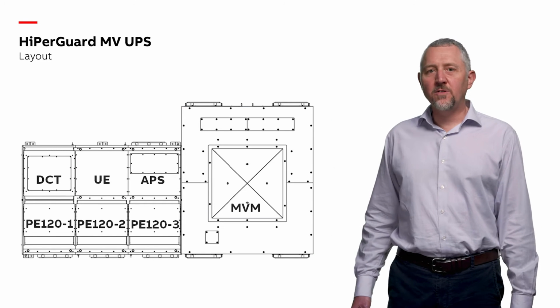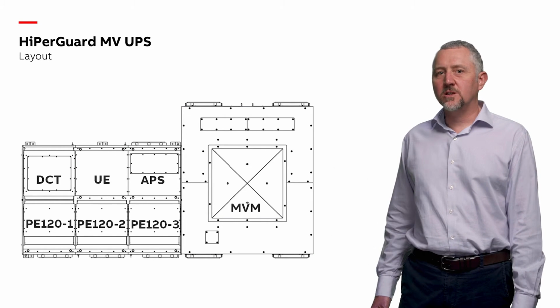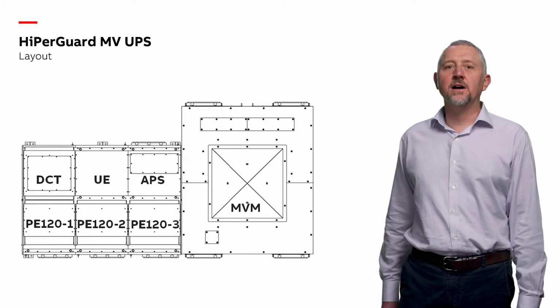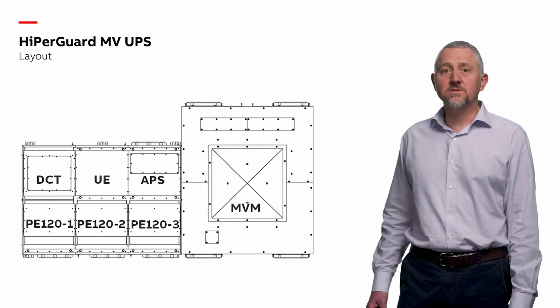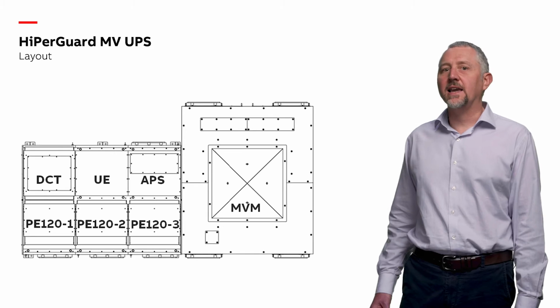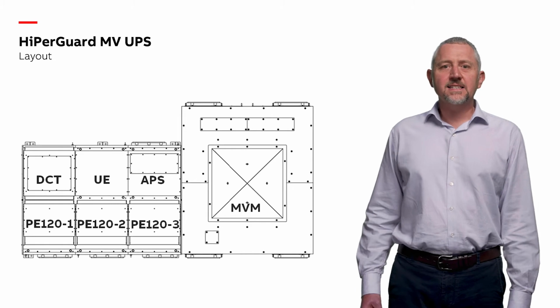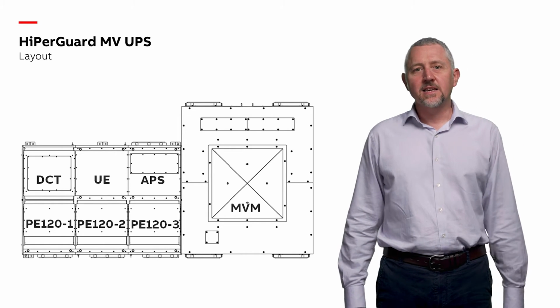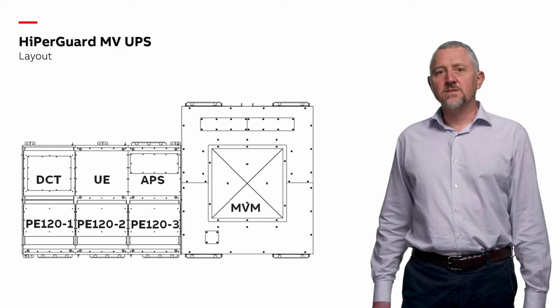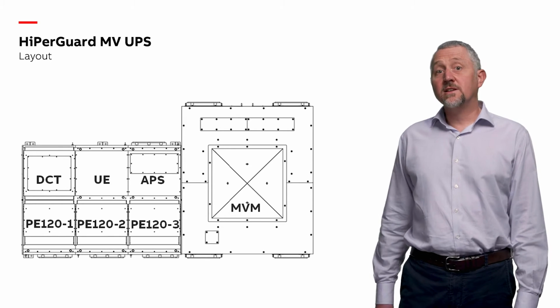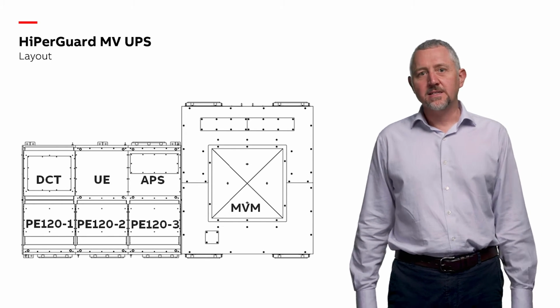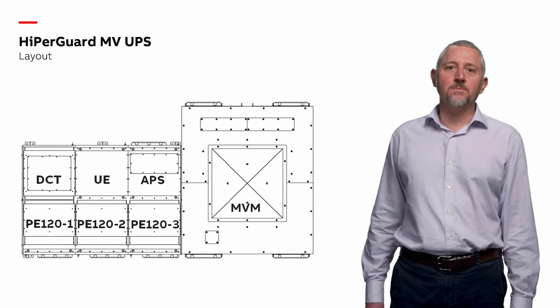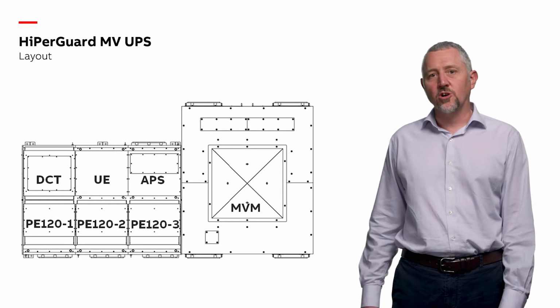Here we see an overhead view of a single 2.5 MVA HiPerGuard unit. Various components contained within each enclosure play a critical role. The DC termination enclosure, DCT, retains the cable connections for the energy storage. The auxiliary power supply enclosure, APS, contains the redundant power supply modules for the system command and control.